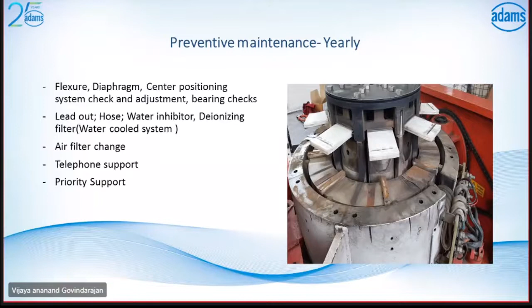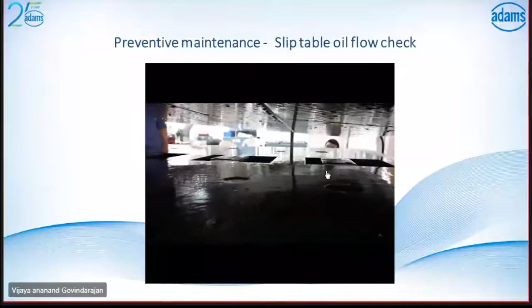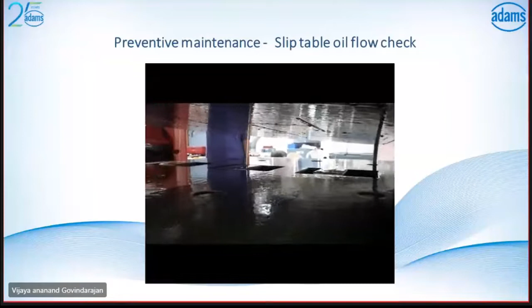This is an example of the slip table movement. You can see, this is the hydraulic bearing slip table. This slip table is hung at a particular distance, and from that, oil is flowing on the bearing. So these are the checks we will do in the preventive maintenance for easy movement of the slip table without any jerks, and it will help to check the bearing movement as well as the shaft.